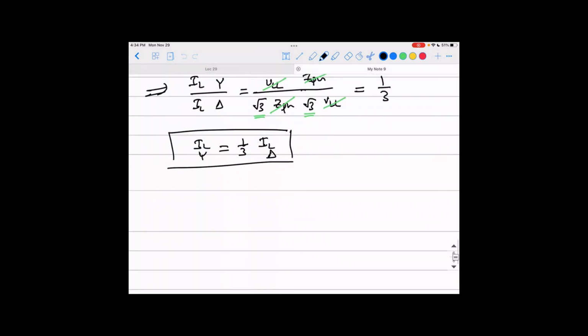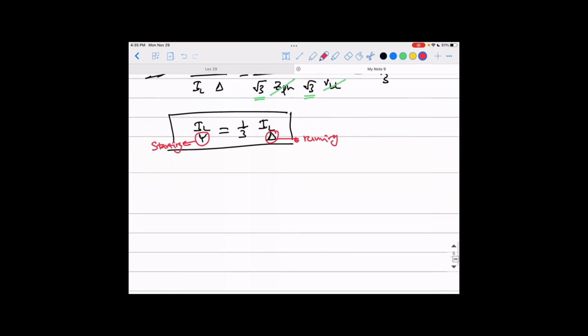Understand what I'm talking about here, guys? We said that the Y connection is the starting connection, while the delta connection is the running connection, yeah? We connect the machine as Y for the starting, and after just past the starting, we go to delta. And that means using the Y delta starter here, I starting is 1/3 of I running. So using this method, you can reduce the starting current by a factor of 3. And that is pretty much sufficient for most of your applications. Okay, guys? And that's why that is the most commonly used method, actually.